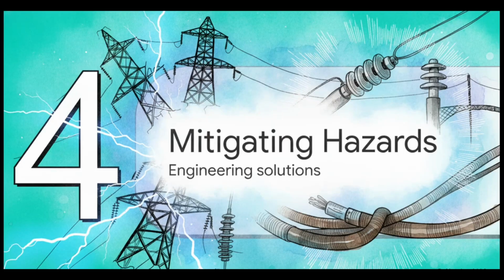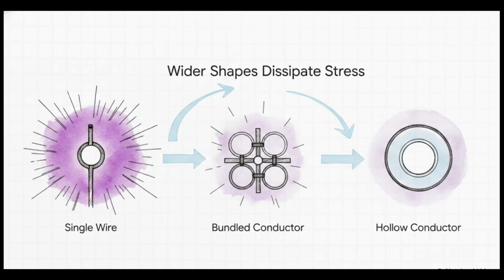Okay, Section 4, Mitigating High Voltage Hazards. How we actually engineer the solution. We've seen physics trying to break the grid apart, so let's look at how we fight back. Let's tackle that first threat. Fighting corona discharge basically comes down to manipulating geometry. Since the discharge is caused by a highly concentrated surface electric field gradient, engineers just outsmart it by increasing the effective diameter of the line, right? A thicker line spreads that electric field out over a much larger surface area, which drops the gradient well below that critical 30 kilovolts per centimeter threshold. And they achieve this cleverly. They use bundled conductors, where several smaller wires are grouped together so they act like one giant wire, or they just use hollow conductors. Problem solved.